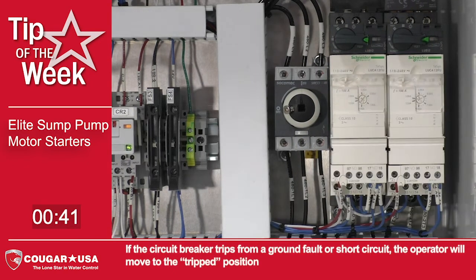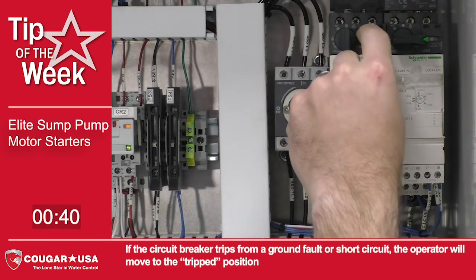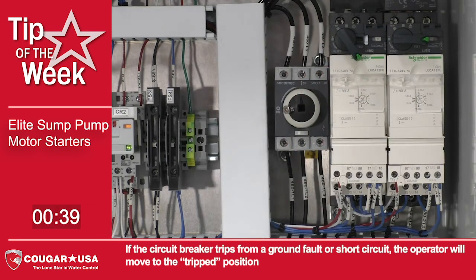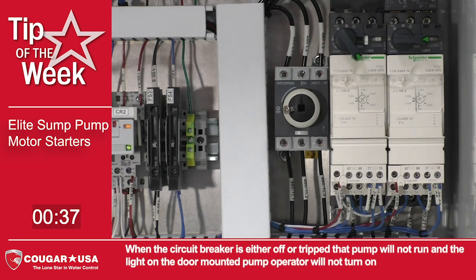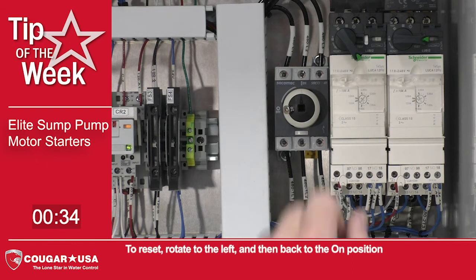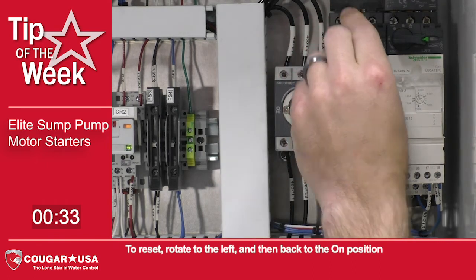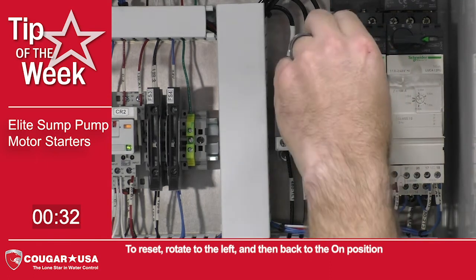If the circuit breaker trips from a ground fault or short circuit, the operator will move to the tripped position. When the circuit breaker is either off or tripped, that pump will not run and the light on the door-mounted pump operator will not turn on. To reset, rotate the operator to the left and then back to the on position.